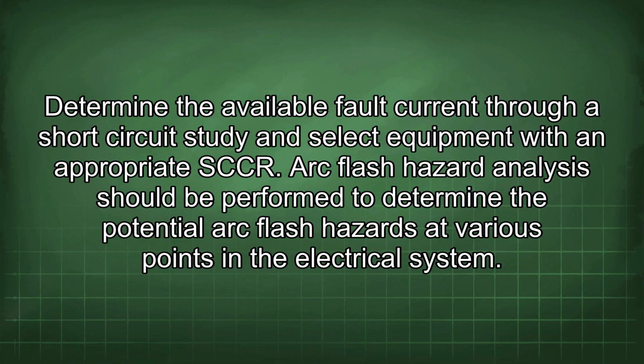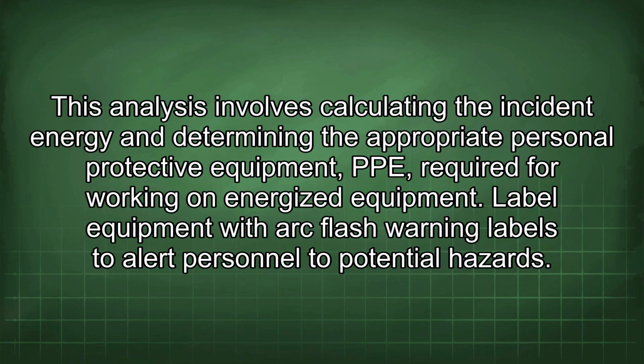Arc flash hazard analysis should be performed to determine the potential arc flash hazards at various points in the electrical system. This analysis involves calculating the incident energy and determining the appropriate personal protective equipment (PPE) required for working on energized equipment. Label equipment with arc flash warning labels to alert personnel to potential hazards.